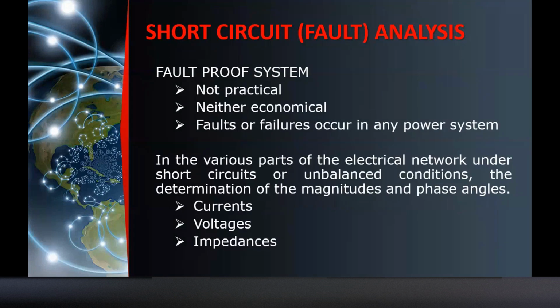So in the various parts of the electrical network under short circuits or unbalanced condition, the determination of the magnitude and phase angles is as follows. Nasusukat natin siya based on currents, kaya nga meron tayong kiloampere interrupting capacity, and we have voltages. Bakit sir voltages? Aware naman tayo pag nagkaroon ng fault, you have a voltage dip. Nagdi-dip yung voltage mo kaya nag-i-increase yung current. So we have also the impedance. Ano yung reaction ng impedance mo based on the available fault level? Mamaya meron tayong basic calculation diyan.